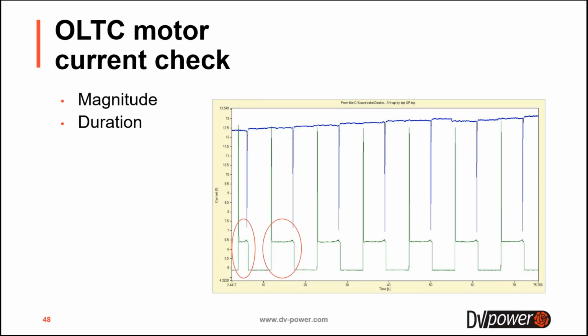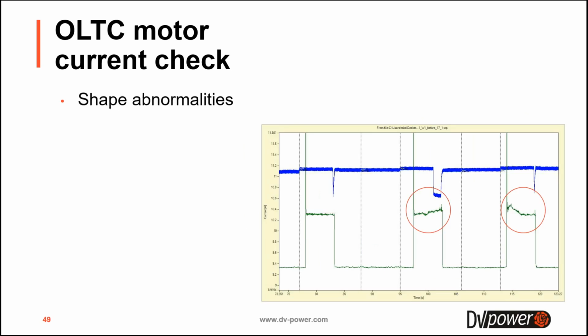We mentioned that together with a DV test, you can record the OLTC motor current. So it also can be useful for detecting some problems, especially problems with mechanisms in gears and stuff like that. What you need to pay attention to is you can check the magnitude, the duration of the OLTC motor current, and you can also check for some shape abnormalities.